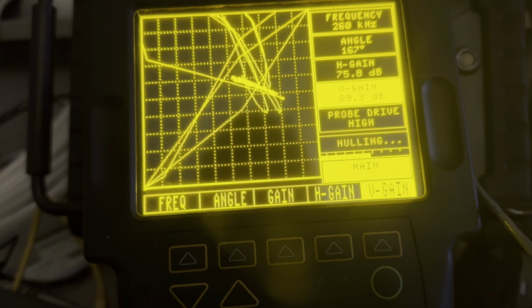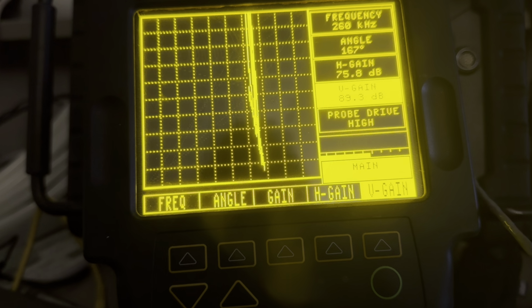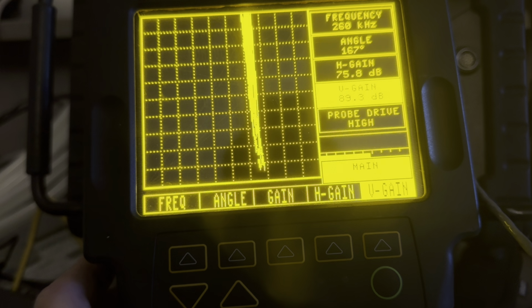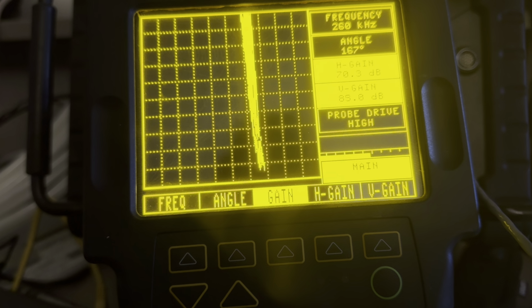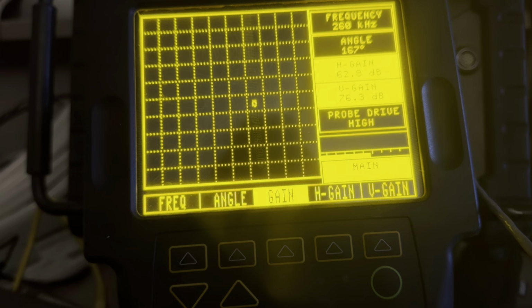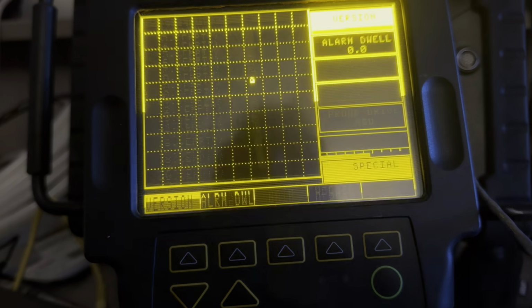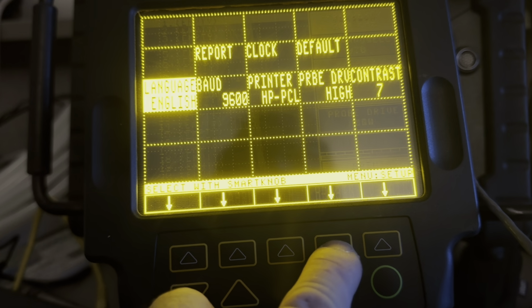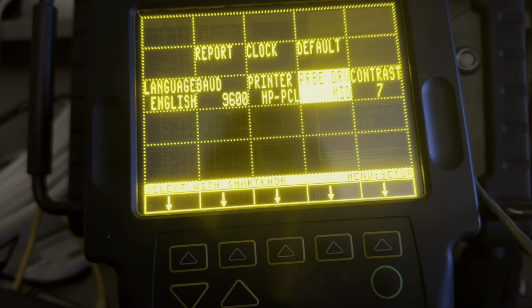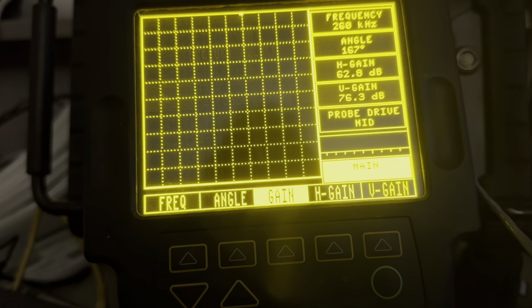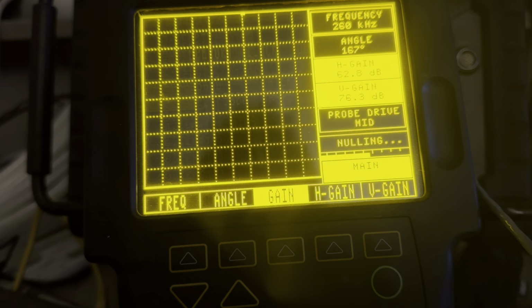I'm going to hit null. Erase. I just want to make sure my probe's working. Okay. Something is wrong with my tester. Well, could that be the gain? I don't know, maybe. Let's crank the gain down a little bit. Okay, something is not acting as expected. So I'm gonna go and try to adjust the drive voltage to medium. And then I'm gonna hit null.